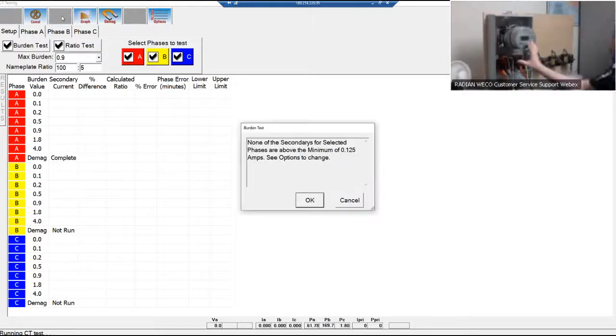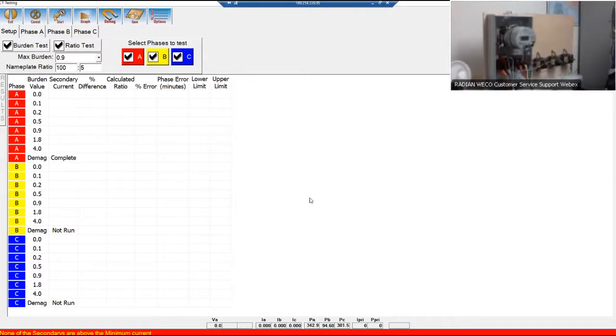I'm going to go ahead and energize my setup here. That's why it's yelling at me. Because as you saw earlier in the options menu, I said do not start a test unless it's 1/8 of an amp on the secondary. Well, if you look down at the bottom of my screen, all my amps are 0. Now that I've got everything in line, I'm safe to energize my setup.